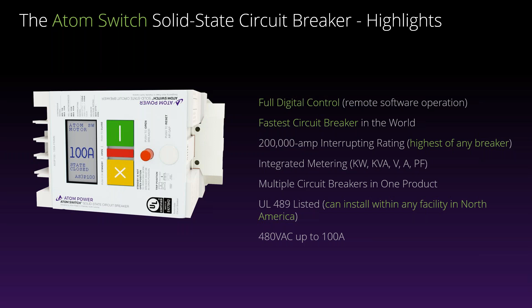Looking inside the breaker, you can see kind of how it works. Well, you've got the control and logic in the firmware on the control board there in the middle, down towards the bottom. This is the power semiconductor where the power flows through the breaker. You've got an air gap disconnect. So what this does is it allows you to mechanically open the breaker. If you need to do any work downstream, you can put a lock through this. So you can follow all of your NEC and NFPA lockout, tagout, safety requirements. And we've got a TVS array in here for transient voltage suppression, allowing for clamping on high inductive loading surging events.